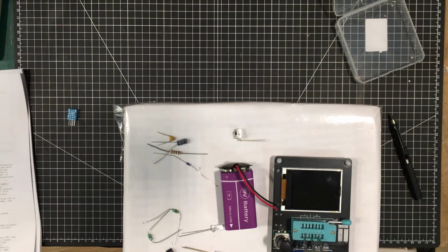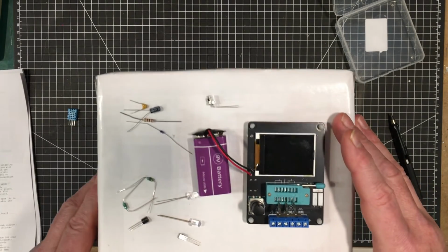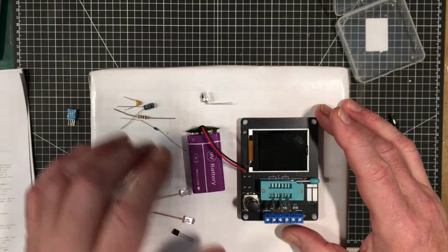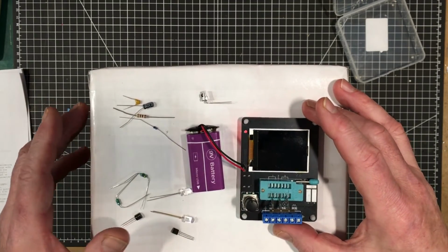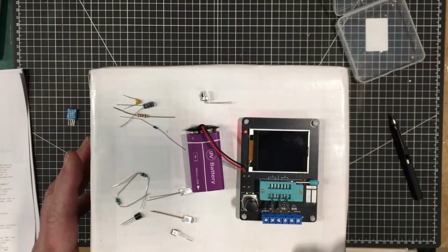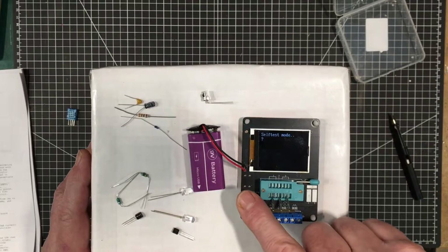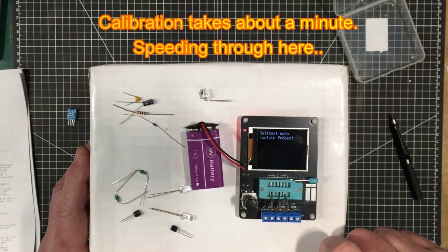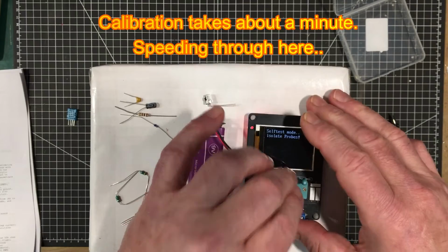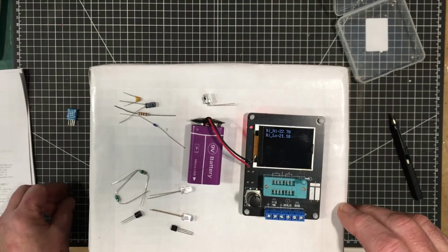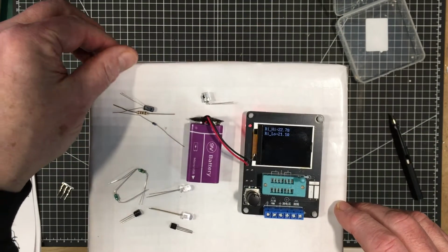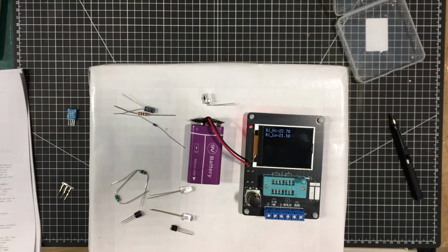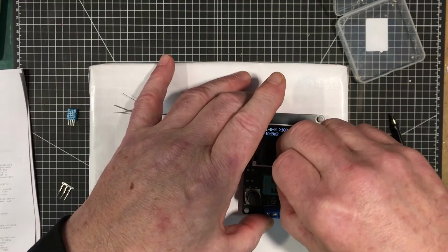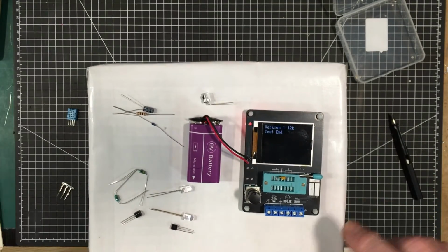Yeah, so let's go through the calibration here to begin with. Let's get this centered on the screen here, and we'll turn it on. So the calibration is a little bit of a dance. It'll self-test mode, yep. Isolate the probes, that means take this thing out. It should continue on by itself. And then it's gonna ask me to put a capacitor in. Okay, yeah, I'm gonna put that in. Okay, that's it. Test has ended.